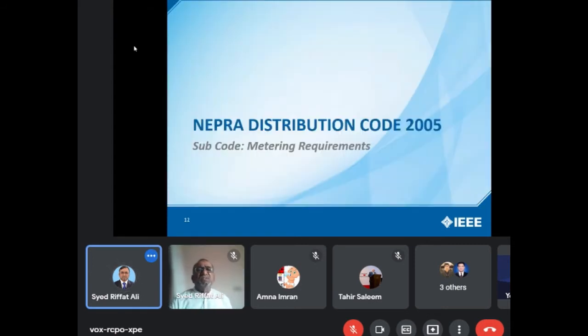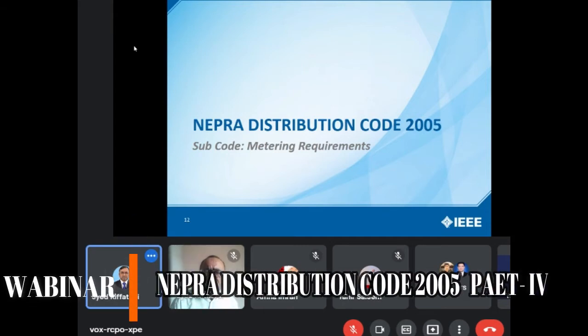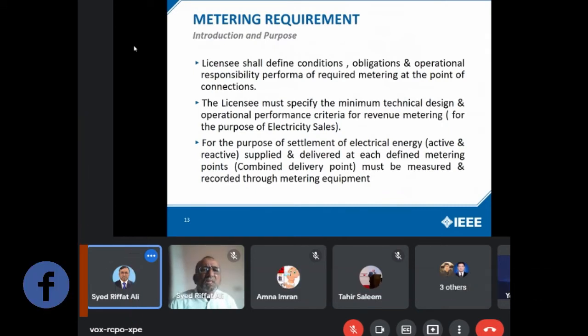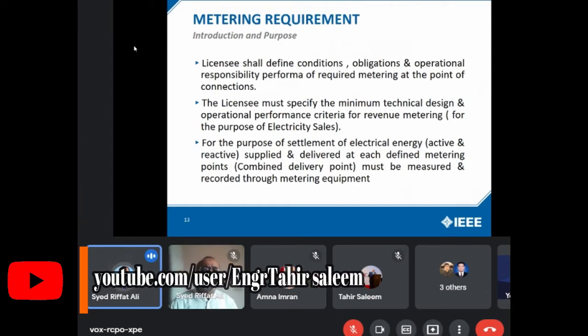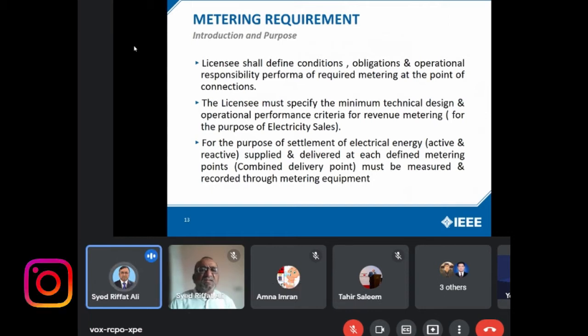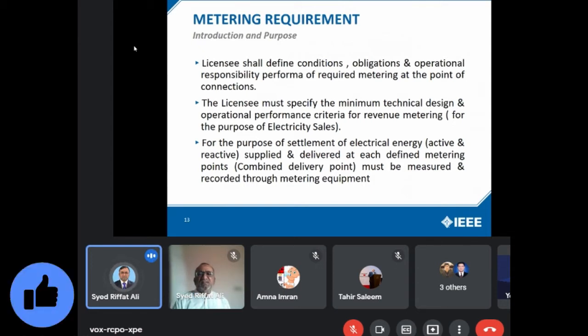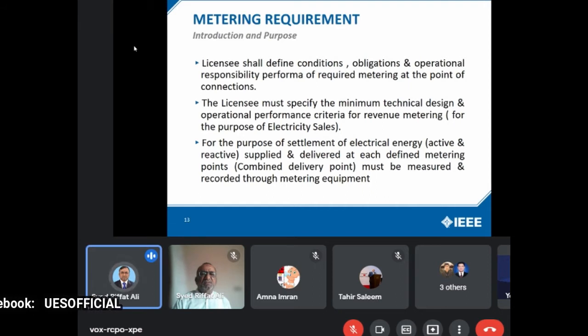Now we switch over to the metering requirement of the distribution code. This is the ninth subcode, and the purpose of this metering requirement subcode is that the licensee shall define conditions, obligations, and operational responsibility of the required metering at the points of connection. The licensee must specify the minimum technical design and operational performance criteria for revenue metering for the purpose of electricity sales. For the purpose of settlement of electrical energy, active and reactive, supplied and delivered at each defined metering point, combined delivery points must be measured and recorded through metering equipment as well.